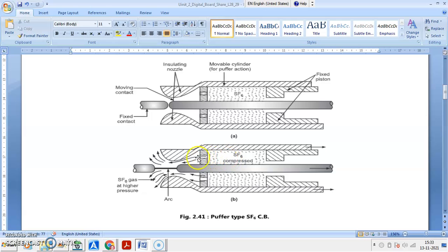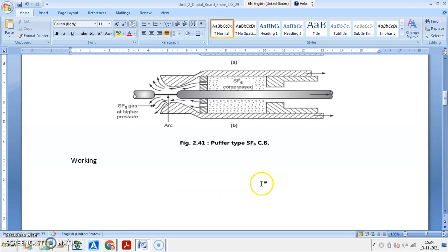So forced high pressure SF6 gas is applied on the arc. When arc is struck between the contacts after separation of moving contact, high pressure SF6 gas is applied over here. This is the puffer action, and arc gets extinguished. So the working of SF6 gas puffer type circuit breaker you have seen. Any doubt?